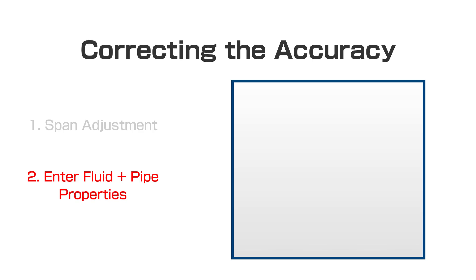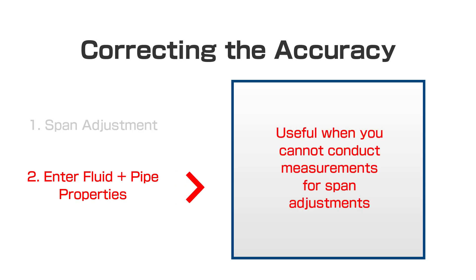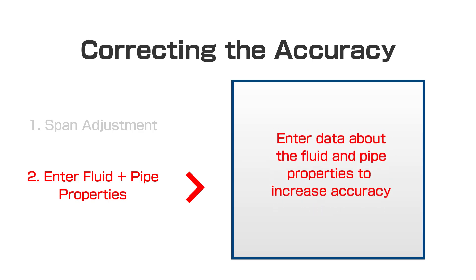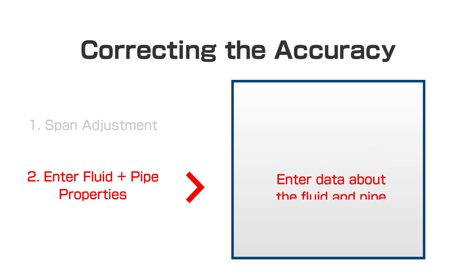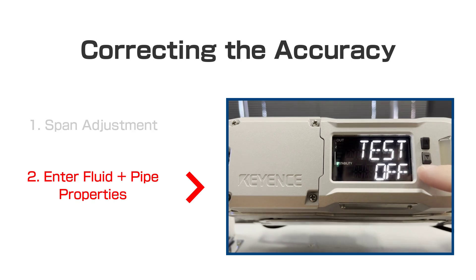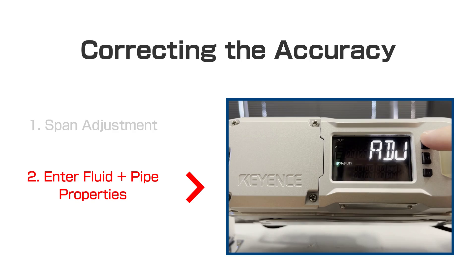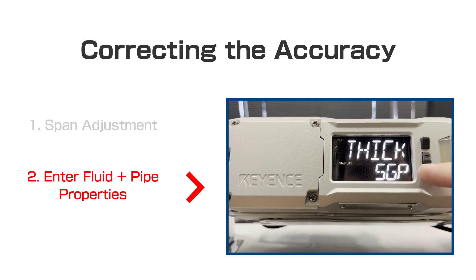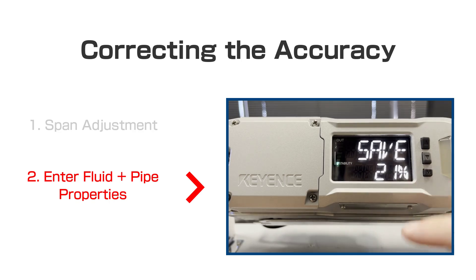If you cannot conduct any tests for the flow rate or volume traveling through the meter, you can still correct the flow rate value by entering pipe and fluid details directly. From the current value display screen, press and hold the mode button, then tap mode until you see 'end'. Tap the up arrow and the screen should change to 'full'. Now tap mode until you see 'ADJ', which stands for adjust. You can choose between entering a span adjustment, covered earlier, or entering additional information about the pipe and fluid under the 'PRO' section. When you tap mode, you'll be able to input the exact outer diameter and thickness of the pipe, the ultrasonic velocity of the fluid, and the fluid's kinematic viscosity. Inputting these settings to the best of your knowledge will help increase the accuracy.